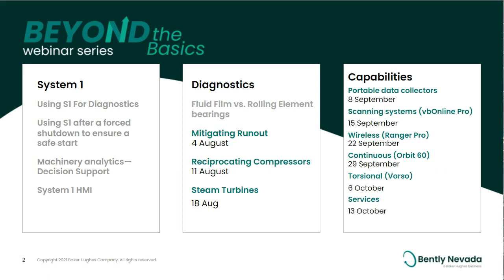The proximity probe offers many advantages over the shaft rider technology that it displaced. No pun intended. Well, maybe there was. It does have one drawback, however, and that's Runout. In this short course, learn what Runout is, how to measure it both at the machine shop and in the machine. Learn how to prevent issues when sending your rotor out for machining. And finally, learn how to properly use runout compensation.